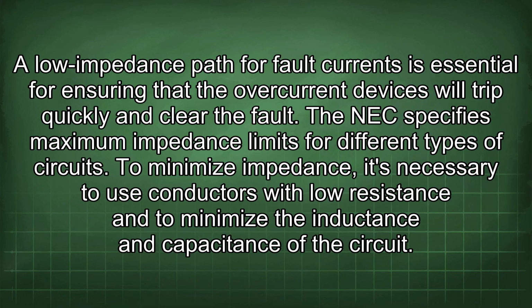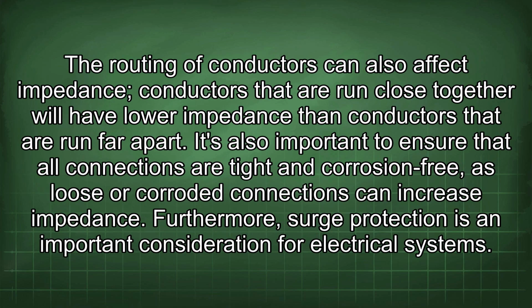To minimize impedance, it's necessary to use conductors with low resistance and to minimize the inductance and capacitance of the circuit. The routing of conductors can also affect impedance. Conductors that are run close together will have lower impedance than conductors that are run far apart. It's also important to ensure that all connections are tight and corrosion-free, as loose or corroded connections can increase impedance.